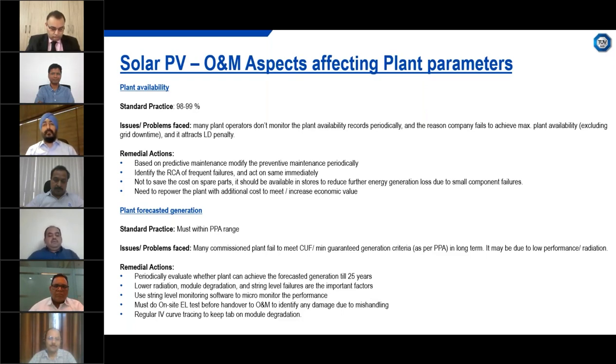We suggest that plant developers must do on-site EL test before handing over to O&M, to identify any damage due to mishandling. Once modules arrive on site and construction and commissioning are complete, and it's handed over to the O&M team, it must be ensured that the complete plant, all instruments, everything is in perfect condition and operating per design norms. The last point is regular IV curve tracing to keep tabs on module degradation, to keep an update on the condition of the modules from a complete project perspective.